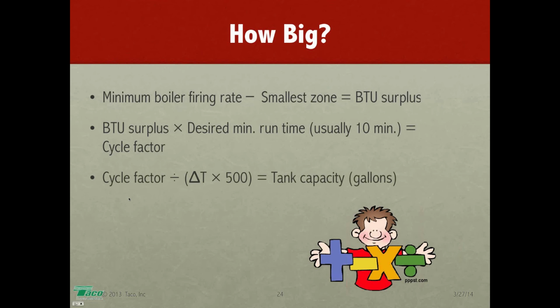Next, to find the size of the tank, we will divide the cycle factor by the distribution side delta T times 500. This will be 20 times 500, or whatever the distribution side delta T happens to be. So not the boiler delta T, but the heating system side delta T. So cycle factor divided by delta T times 500 will give you the tank capacity in gallons.